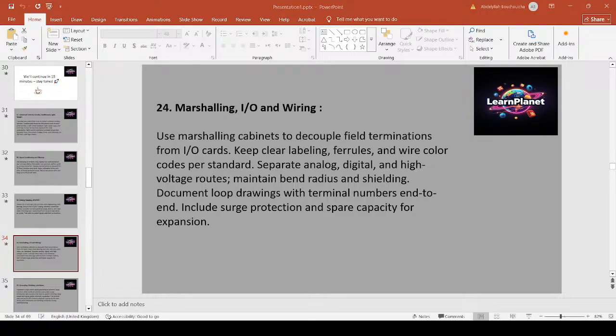Marshalling cabinets decouple field termination from control room I/O modules, simplifying replacements and labeling. Use clear field IDs. Maintain wiring diagrams that map field tags to marshalling terminal to I/O card. Separate analog, digital, and power wiring physically to avoid crosstalk. Follow bend radius and gland practices. Include spare channels and surge protection in marshalling for future expansion. Example: during site acceptance test, trace each loop from field junction box to marshalling and confirm terminal numbers match loop drawings.